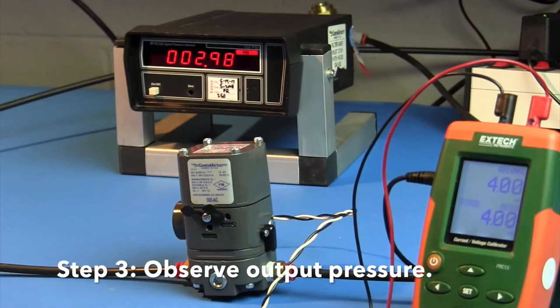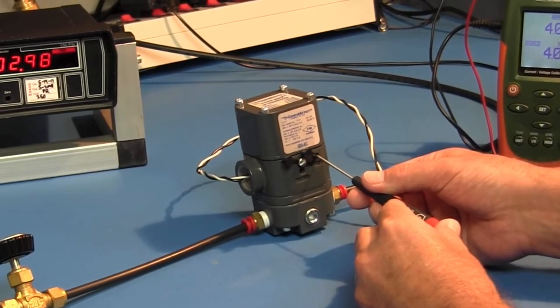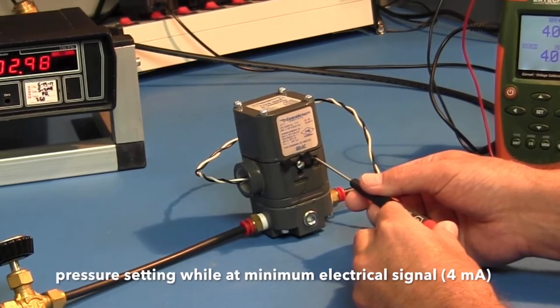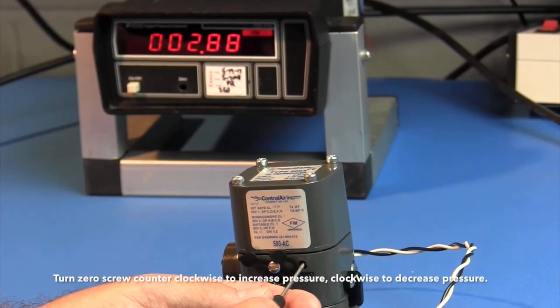Step 3. Observe the output pressure. Adjust zero screw until reaching minimum output pressure setting while at minimum electrical signal. Turn zero screw counterclockwise to increase pressure, clockwise to decrease pressure.